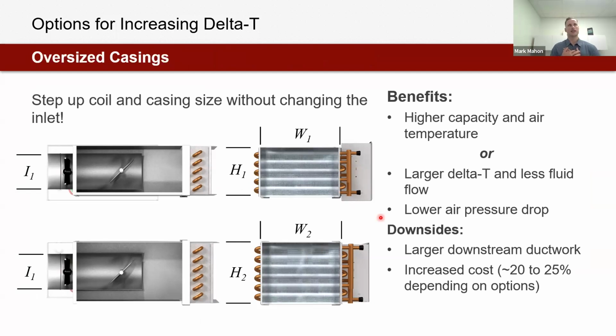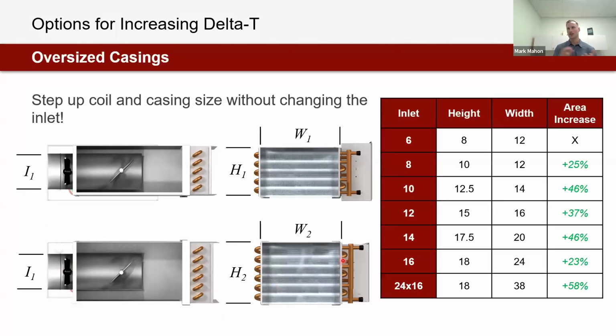And the thought process here is, let's step up the coil and casing size of the single duct without changing the inlet size of the single duct. Here, we're going to get, once again, that larger delta T or less fluid flow rate, but we're also going to get lower air pressure drops. So that's going to help with our fan energy index and the fan efficiency for the system. The one downside is we are going to get larger downstream ductwork, and the cost of this option is a little bit higher than, let's say, a high capacity coil, because we're making the whole product a little bit bigger. And just for scope of that, how much bigger is it actually getting?